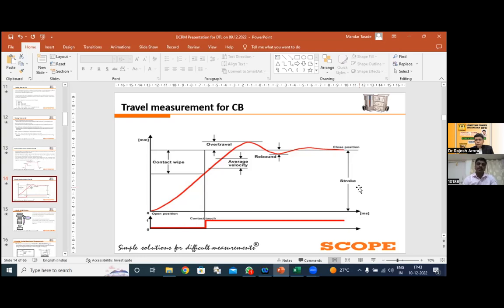Normally, as per the practice or the thumb rule, we are taking the datum velocity between 20% and 80% of the travel, where we get the velocity called the datum velocity. I hope this point is clear to all, because this is a very important parameter associated with the travel measurement.